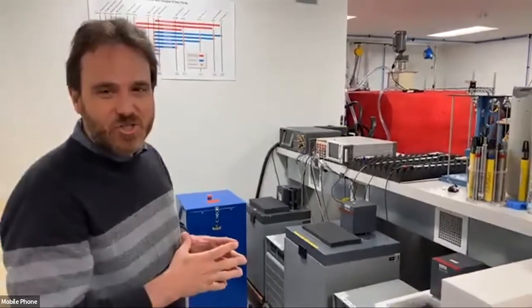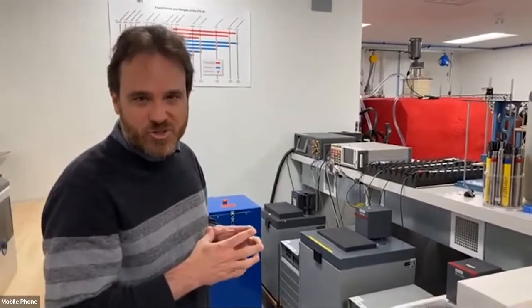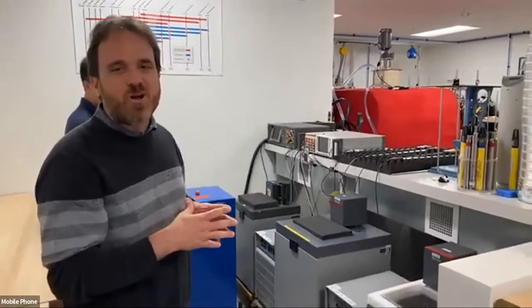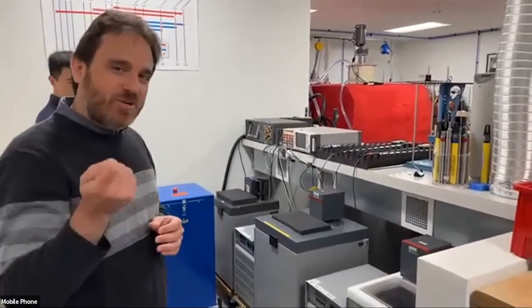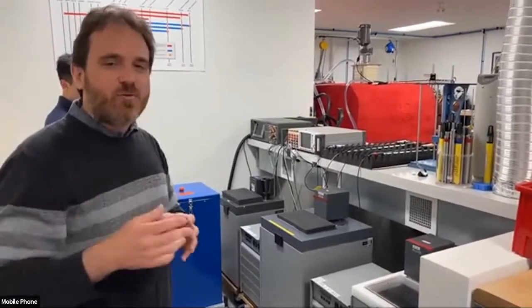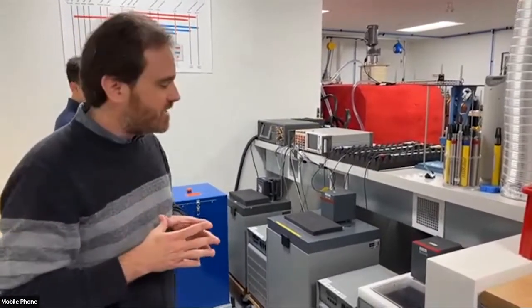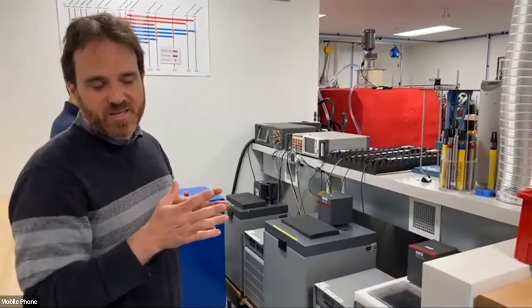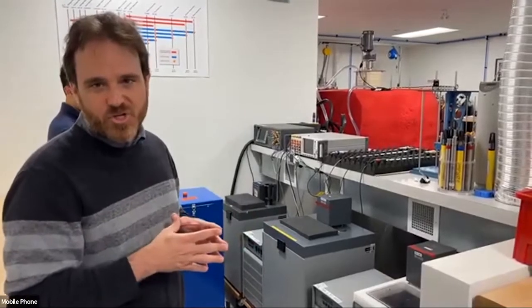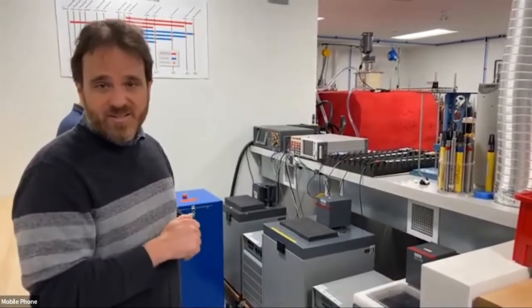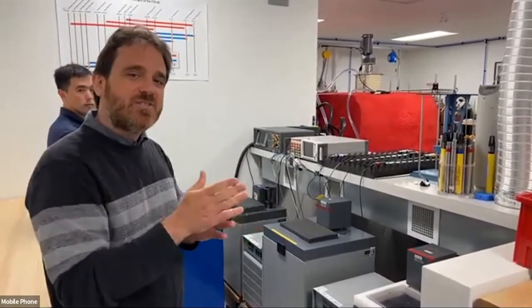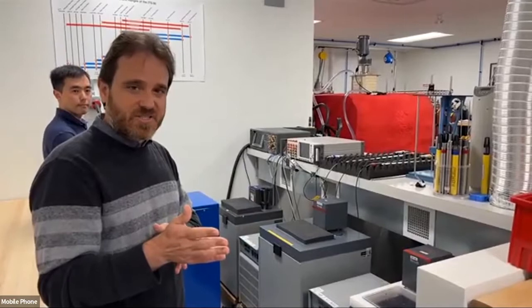In a little while, I'll get to show you the triple point of water cell that we actually use to do our verifications. So we'll get to that in a minute. Let me just start by explaining more or less the overall process. Once a unit is received, either from production or from the service department, as Mark was explaining, the first step of the process is to put the instrument through our temperature calibration. We do an 8-point temperature calibration throughout the range of -5 degrees Celsius to 35 degrees Celsius.